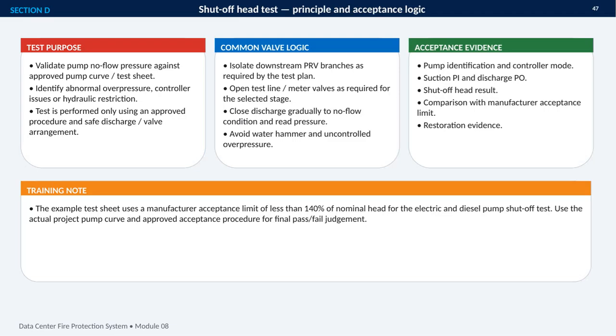This section explains the principle and acceptance logic behind a shutoff head test. The purpose is to verify the pump's no-flow pressure against the approved pump curve or test sheet, while also identifying potential overpressure, controller problems, or hydraulic restrictions. Because the test can create significant pressure, it must follow an approved procedure with a safe discharge and valve arrangement.